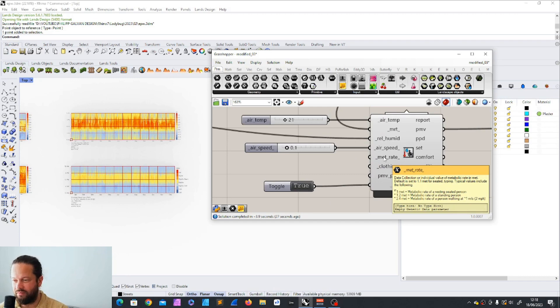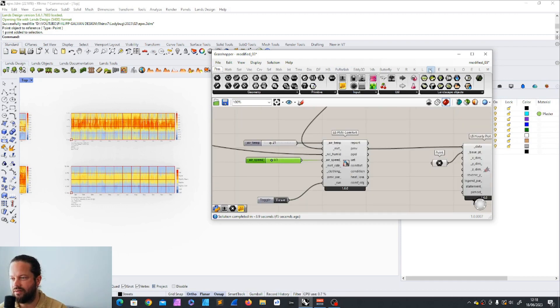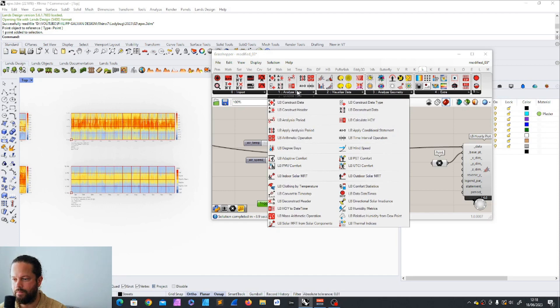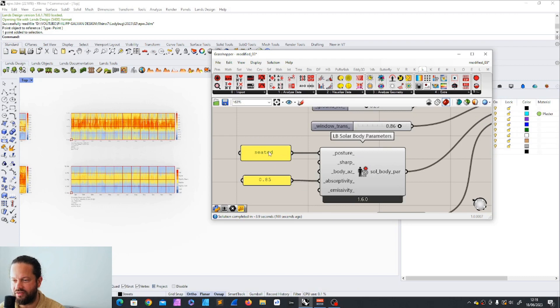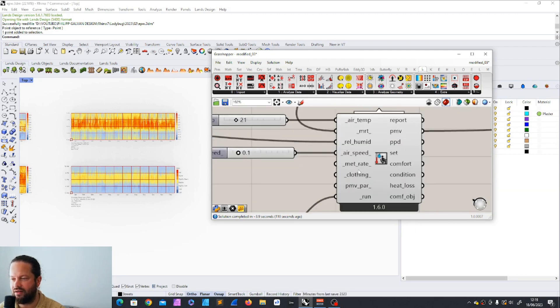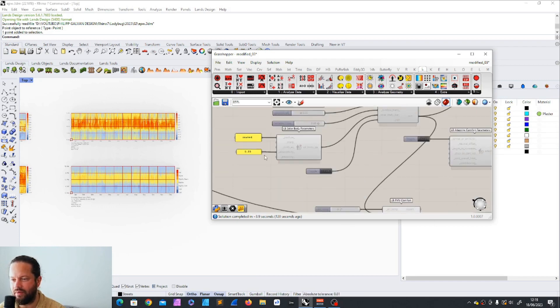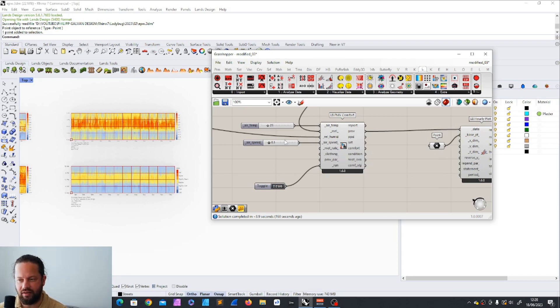The metabolic rate — we talked about this before. We actually used the metabolic rate in the PET comfort. The metabolic rate is the equivalent for posture here — seated, standing, or supine. It's just a number. One MET would be the metabolic rate of a resting seated person; 1.2 for a standing person; 2.4 for a person walking. The default is 1.1, which is seated working. So let's leave that.